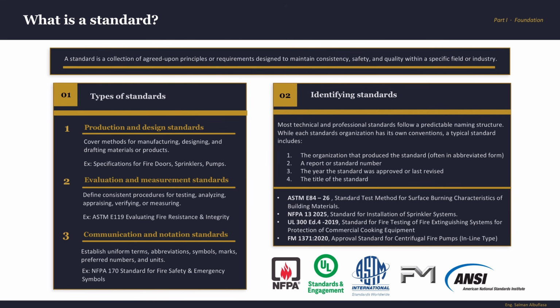Are all standards the same? No. They fall into three main categories: production design standards, evaluation and measurement standards, and communication and notation standards. The first is related to how something is manufactured, designed, and drafted. The actual making of the product. In our field, let's say the specification for fire doors, sprinklers, and pumps. For example, NFPA 20 covers fire pump design, everything from the impeller materials to minimum flow rates and pressure requirements. So these standards are actually the DNA of the product. If you follow them, the thing you build will be right.